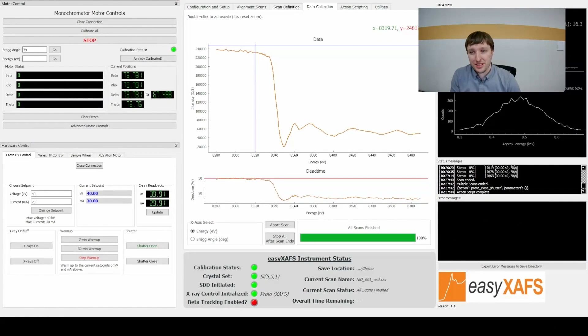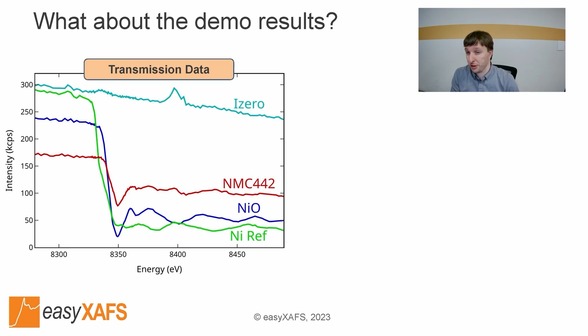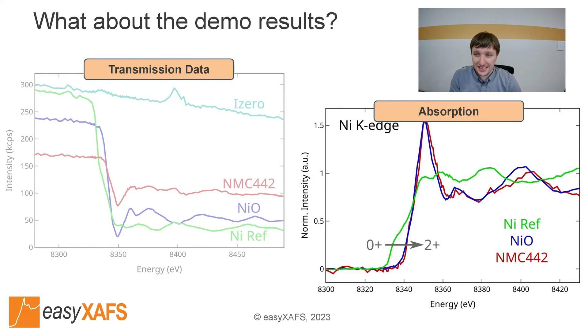Now, as we have been going through these case studies, you have seen the real-time acquisition of rapid XANES measurements on the easyXAFS spectrometer. Here we can now see the transmission data for each of the 3 samples along with the corresponding beam intensity that has been collected as part of the demo measurement. With limited processing, we can convert the transmission results into corresponding absorption spectra. In the absorption spectra, there's a clear shift between the nickel reference 0 and the 2+ nickel oxide and NMC442 samples. In addition, there are slight differences between the NMC442 nickel oxide materials associated with differences in structure. This short measurement highlights the capabilities of XANES to give us direct insight into the oxidation state, even within a few minutes of measurement.